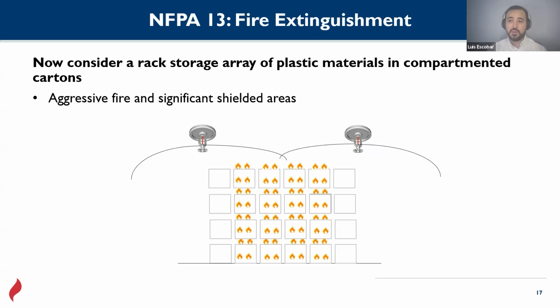The heat release is going to be way higher. The sprinklers by themselves are going to be a different model, even bigger. The orifice is going to be larger, so the water can be released more efficiently. The pipes, that's the problem when we have a project with big diameters. We all know everybody suffers when it gets to coordination, right? So these two systems are going to be totally different, talking about pipe sizes, sprinklers, and probably the orientation of the sprinkler head.